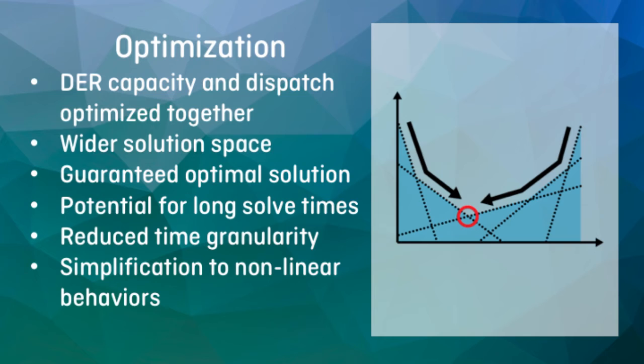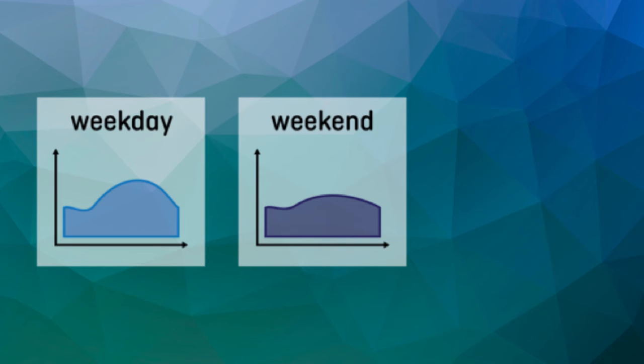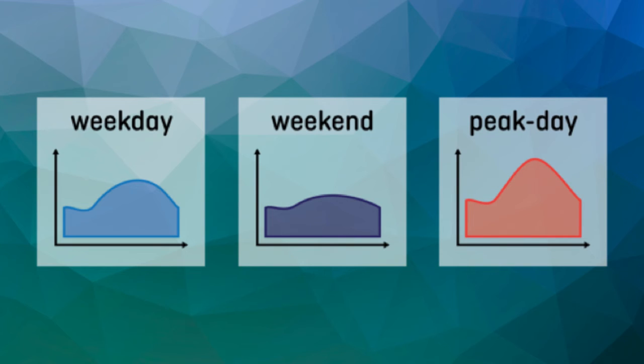There are two major simplifications in DerCam that should be highlighted here. The first being design days. Rather than modeling each day of the year, DerCam uses a smaller set of design days to capture seasonal and operational variation. By default, DerCam uses 36 design days — one for each month across three day types: typical weekday, typical weekend day, and peak day. This peak day type is intended to represent the three days each month where loads are highest, as it is typically these days that will set electricity demand charges, which can comprise a significant fraction of monthly electricity costs and can thus have a lot of influence over optimal system design. Users can add additional design day types to capture events like outages, demand response events, or critical peak pricing events, but in general the variety of days is reduced significantly compared to a full 365-day design period.